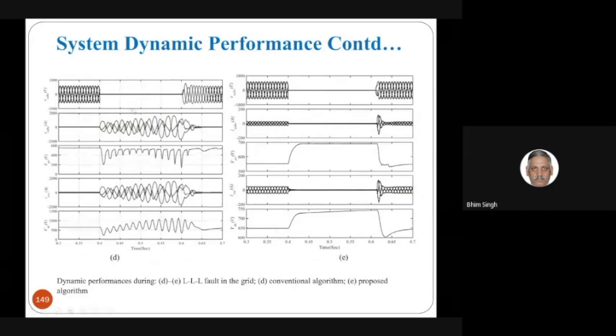And when there is a fault, because nowadays new standards have come, when you have a fault your inverter should remain connected to the grid, because once the fault is removed you can quickly come to steady state. You should also be able to feed some reactive power, if required, to the grid under fault conditions.